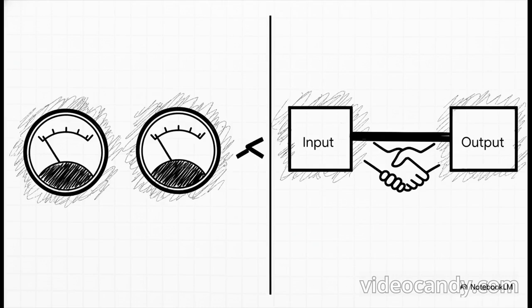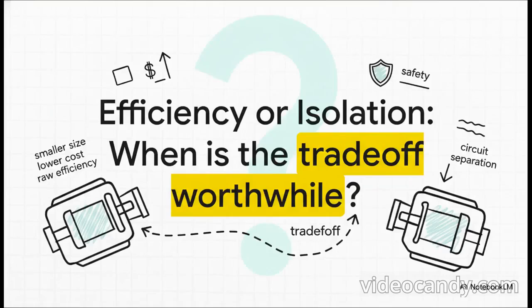So here's the most important takeaway: the benefits of an autotransformer are biggest when the input and output voltages are pretty close to each other, when that voltage ratio is near 1-to-1. And just as importantly, you only use them in situations where that direct electrical connection is safe and acceptable.